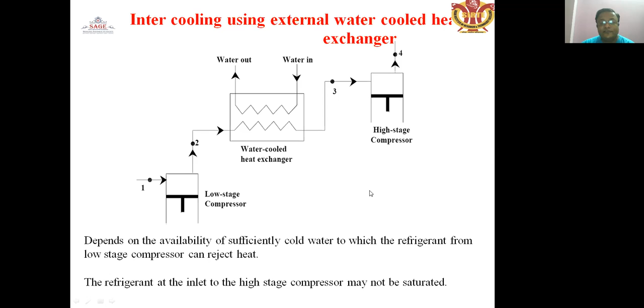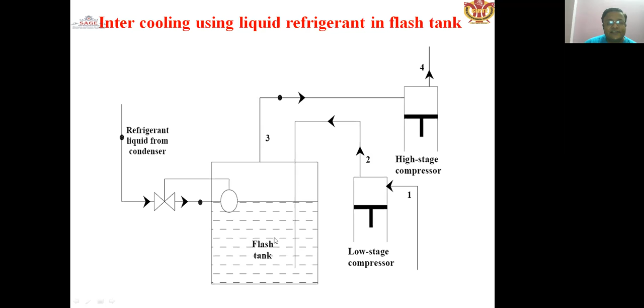Intercooling using the liquid refrigerant in the flash tank. This is the diagram showing the flash tank, the low stage compressor and the high stage compressor. There is a device where refrigerant liquid from the condenser is used. It comes from the side and goes into the flash tank, and after leaving it at point 3, it goes to the high pressure stage compressor. The low stage compressor discharge goes to the flash tank, removing the flash gases. This is a simple arrangement in which the refrigeration effect will be increased.